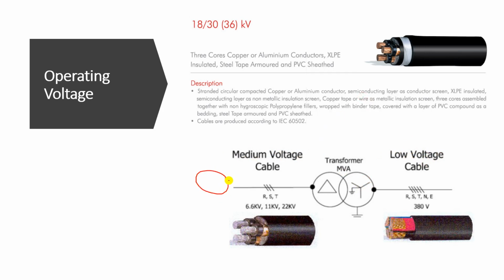So simply, here we have the medium voltage, and here we have the low voltage at which we supply power to our loads. Now the delta connection has three wires, or three cores required. The three wires are RST, or red, yellow, blue, or the three phase. We don't need the neutral or the ground here.